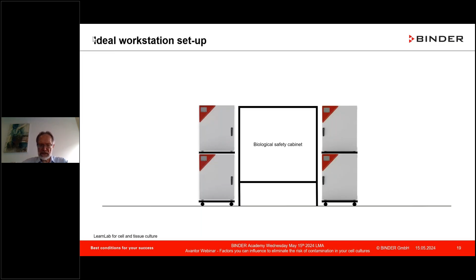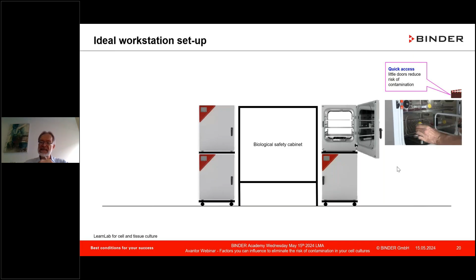Then we have different possibilities. Here you see a little quick access - it's one little door and a big glass door. All CO2 incubators do have this big glass door. This little one right here allows you quick access of maybe a couple of flasks for preheating or preconditioning. And the big advantage right here is the conditions inside remain rather stable compared to opening the big door, and the area where contaminants can enter is much, much smaller compared to opening the big glass door.